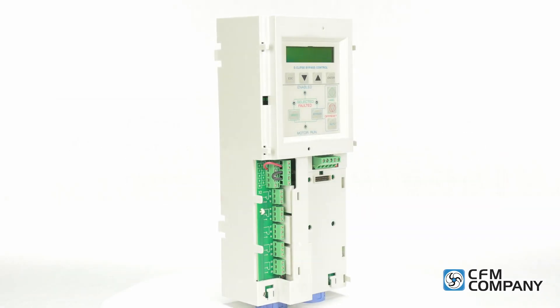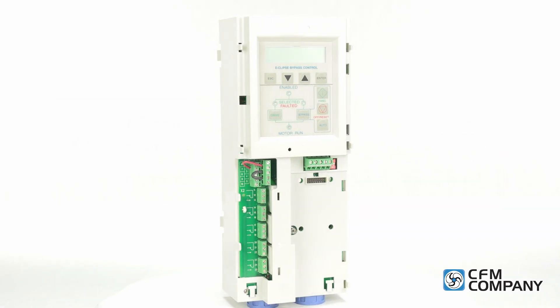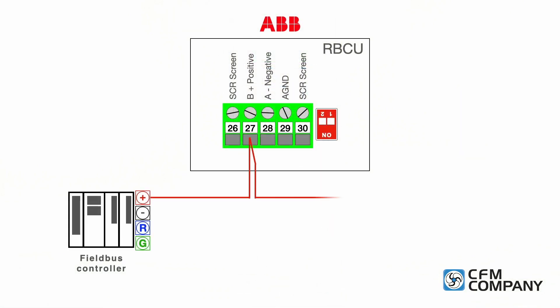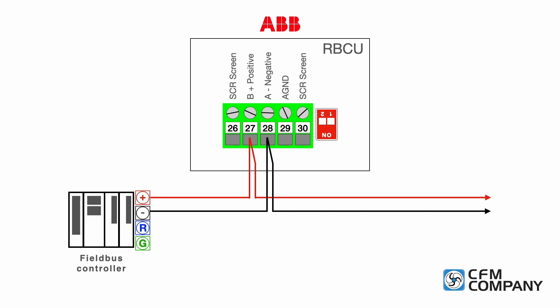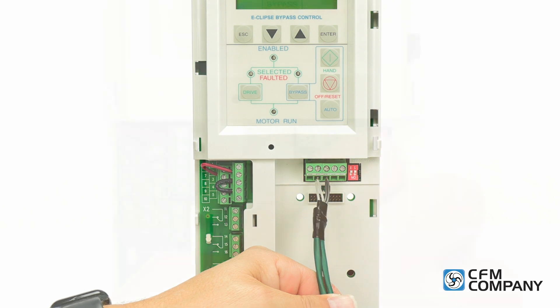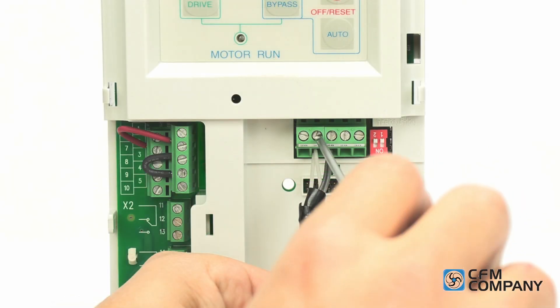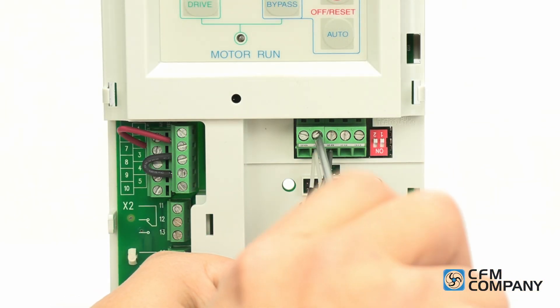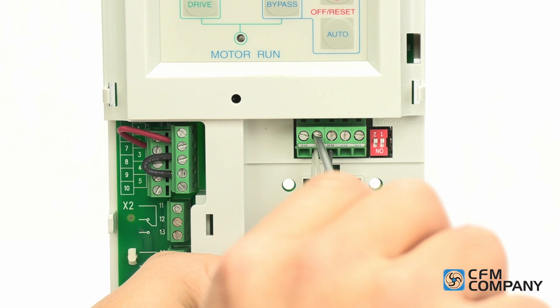Remove the front cover to expose the control terminals. On drives with an Eclipse bypass, the serial communications wires will be landed on the horizontal terminal on the bypass control unit, RBCU. Connect the positive network wire to terminal 27. In our example, this is the white wire.